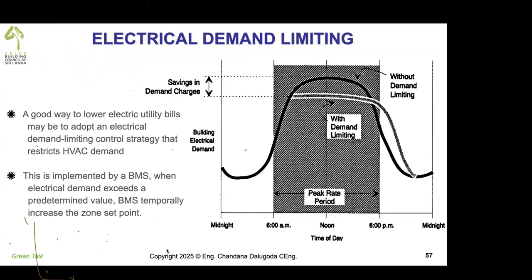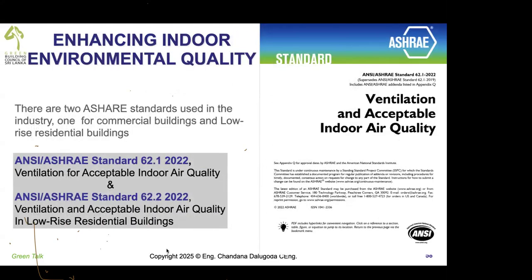Electrical demand limiting is another one. When the demand is going higher than the usual monthly level, this is tracked by the BMS, which sends a signal to all the DDCs where the set points of the AHUs are raised. Normally the set point is 24 degrees C, raised instantly to 25 degrees C. So the chiller will unload, and it will not go above the demand limit. So that's how you reduce energy.